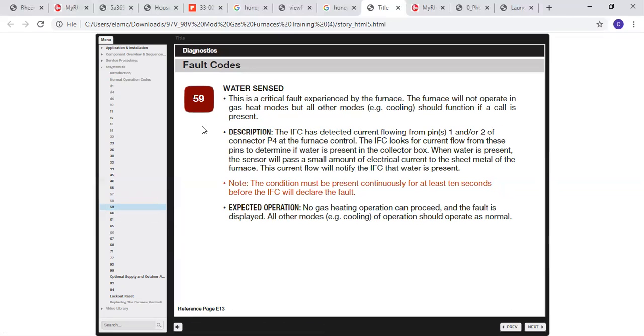Now here's your water sensed. You'll eventually get this at some point with all 90% furnaces from Rheem. If it's brand new or it's a dry trap, you'll get the 59 error code with the self-priming feature. This is a critical fault. The furnace will not operate in any gas heat mode, but it will still operate in cooling and fan.